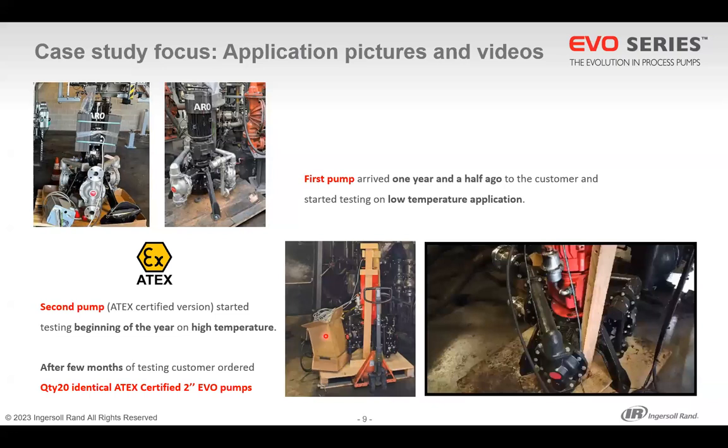Here are some pictures of the two pumps. Of course, you can see we're testing pumps. So the setup is a bit provisory. I mean, it's not a definitive setup, but you can see the first pump arrived and was installed in the outside area, so a low temperature application, and it happened more or less 1.5 years ago.